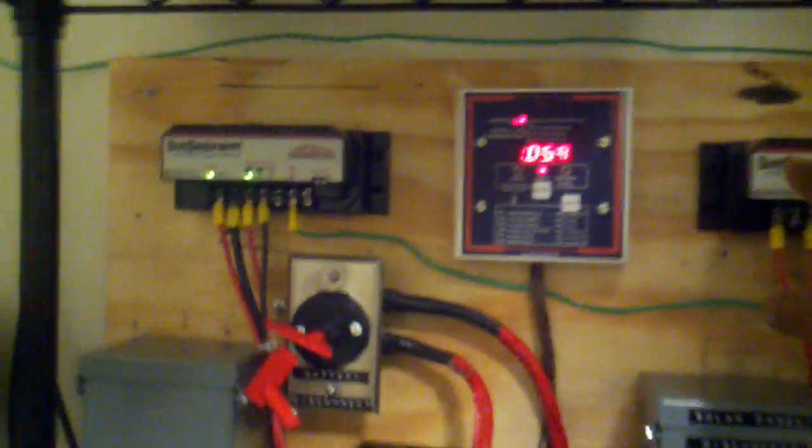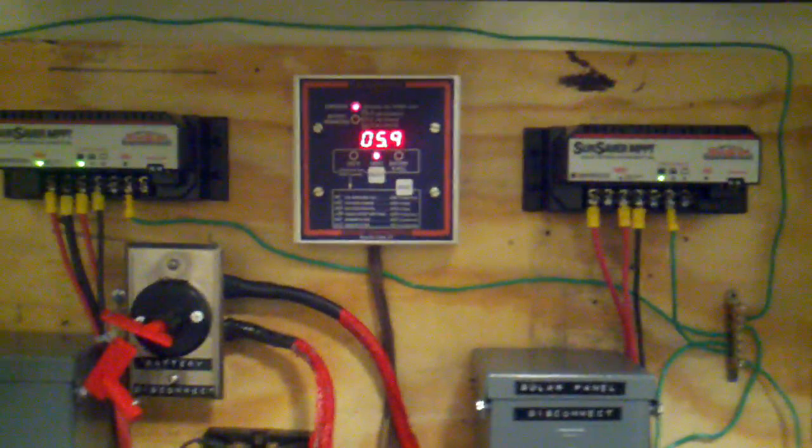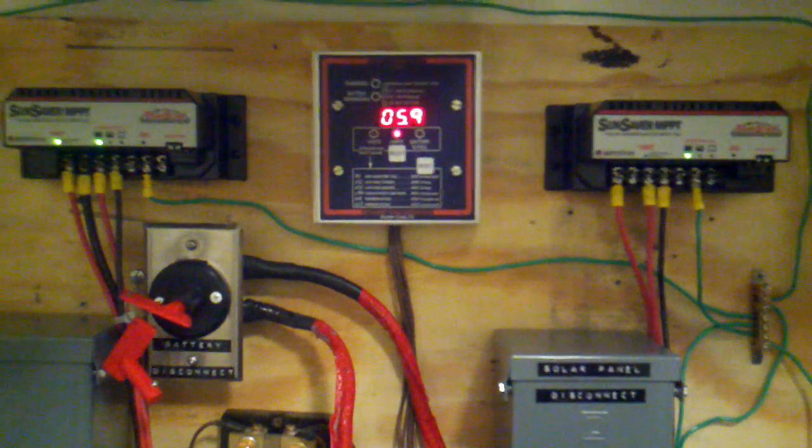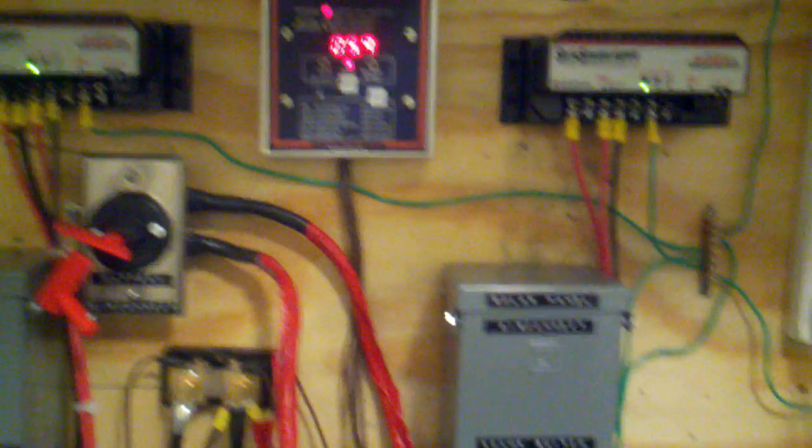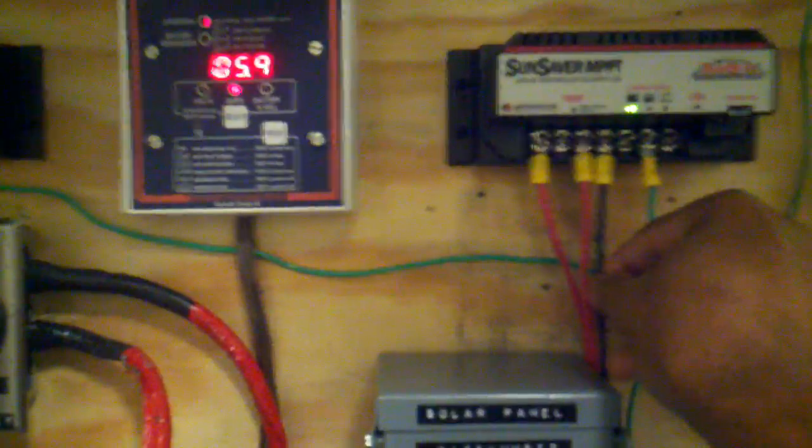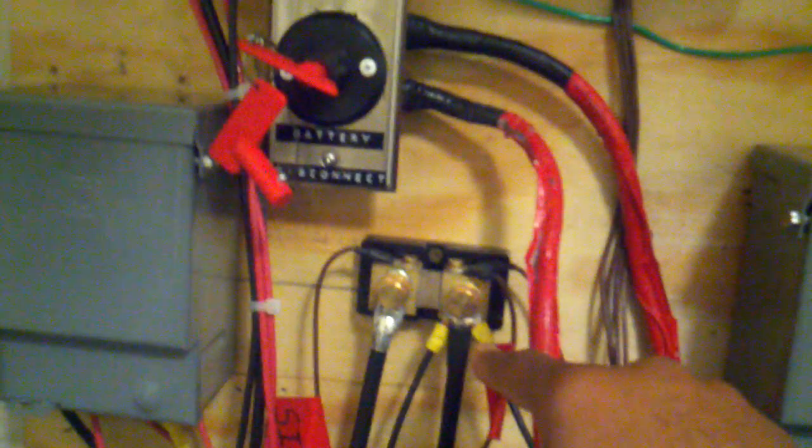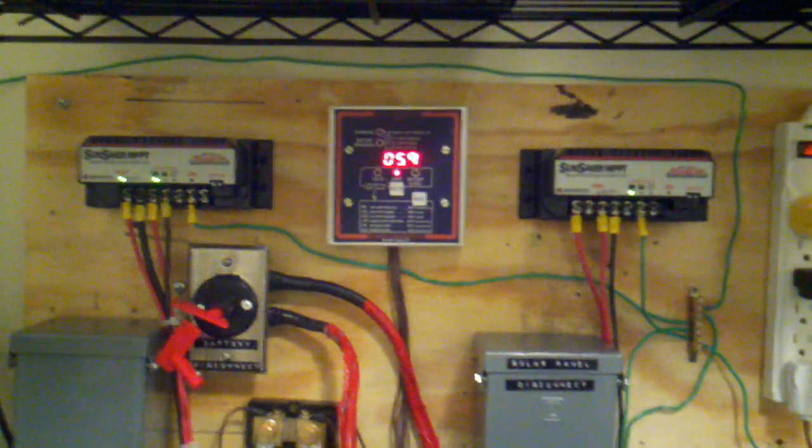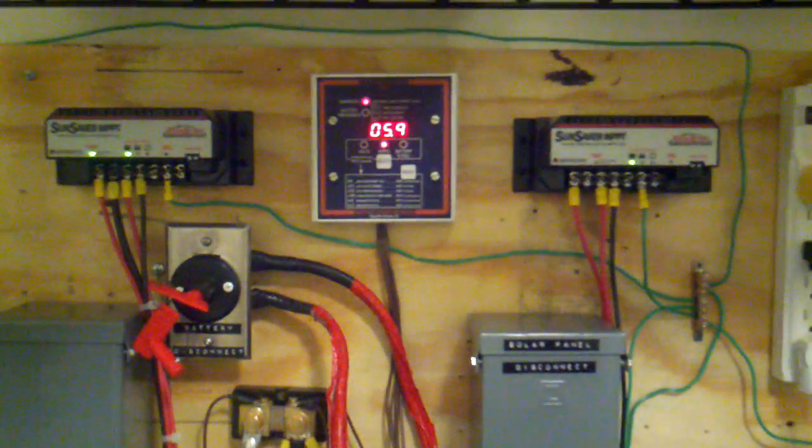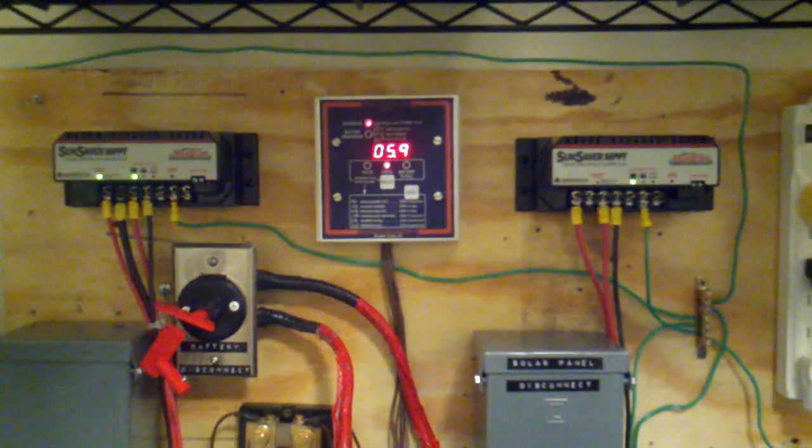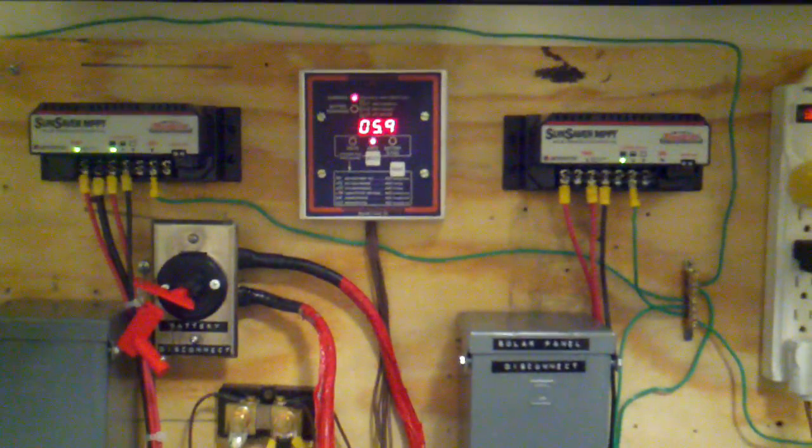Now, with these charge controllers, I looked at research and they said, in order to have both of them, you have to have some type of communication circuit from this charge controller to that charge controller. That's not true. With the Sun Saver by Morningstar or these MPPT charge controllers, the way they're tied in is the negative lead right here that goes to the battery is actually connected in parallel with this charge controller at the shunt. As far as the positive leads, they're connected also in parallel on this main battery lug on the first battery.